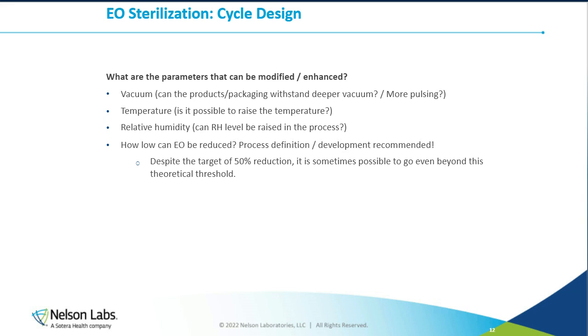So it means that temperature is a really key driver, and it is probably more important when we decrease ethylene oxide concentration, because we have less EO available to sterilize, so we need to increase the pace of the chemical reaction. Relative humidity is also a good driver. It improves the gas diffusion process, working as a catalyst, but it is also adding less resistance to the spores. It can help the spores to become vegetative and be easier to sterilize.